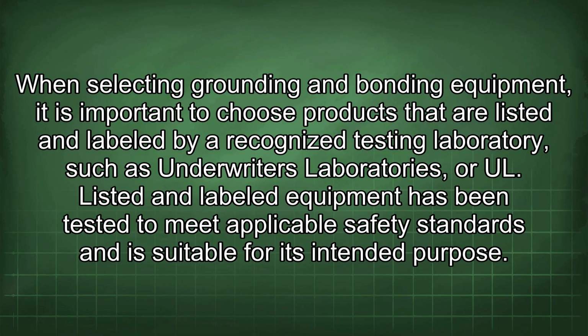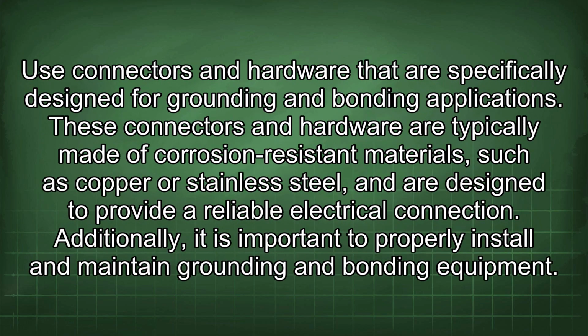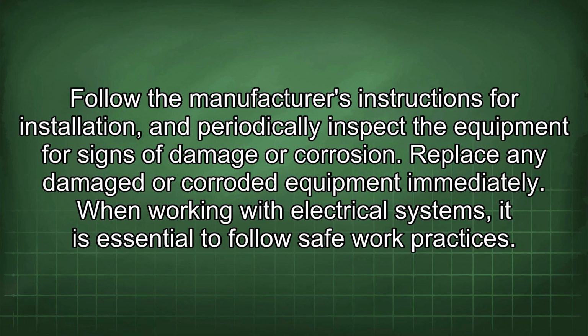When selecting grounding and bonding equipment, it is important to choose products that are listed and labeled by recognized testing laboratories such as Underwriters Laboratories or UL. Listed and labeled equipment has been tested to meet applicable safety standards and is suitable for its intended purpose. Use connectors and hardware that are specifically designed for grounding and bonding applications. These connectors and hardware are typically made of corrosion-resistant materials such as copper or stainless steel and are designed to provide a reliable electrical connection. Additionally, it is important to properly install and maintain grounding and bonding equipment. Follow the manufacturer's instructions for installation and periodically inspect the equipment for signs of damage or corrosion. Replace any damaged or corroded equipment immediately.